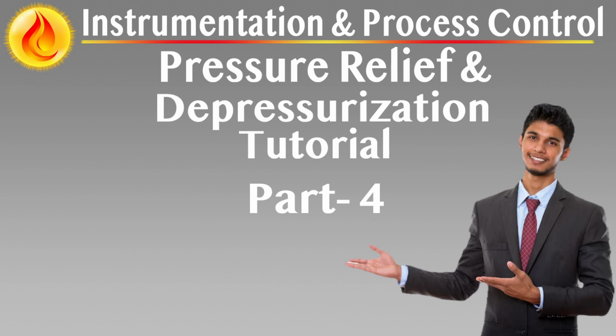Velocity limits and future expansion. To maintain safe operation and accommodate future plant growth, main relief headers should not exceed Mach 0.5 or higher under design conditions. Subheaders may operate at higher velocities, but should generally stay below Mach 1.0.